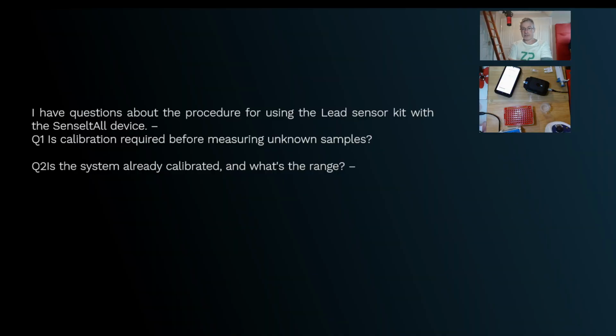Drinking water in the US and Europe, people are interested in measuring things like 4 parts per billion or 5 parts per billion. And therefore, actually, that's quite low, so we don't want to use a high concentration. But if somebody's using this in a mining operation, where maybe there's lead mining, for example, the lead would be really high. So there you could understand that you'd want a 1 in 100 calibration. So we have quite a dynamic range. But we introduced the 1 in 2 dilution because a lot of drinking water applications are really quite dilute in lead.